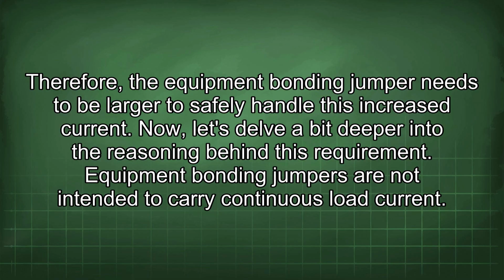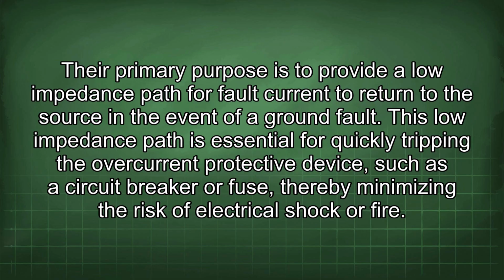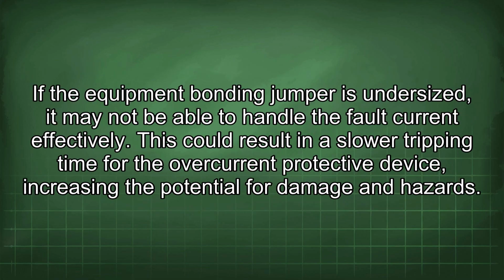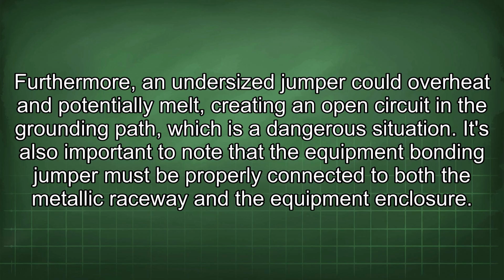Now let's delve a bit deeper into the reasoning behind this requirement. Equipment bonding jumpers are not intended to carry continuous load current. Their primary purpose is to provide a low impedance path for fault current to return to the source in the event of a ground fault. This low impedance path is essential for quickly tripping the overcurrent protective device, such as a circuit breaker or fuse, thereby minimizing the risk of electrical shock or fire. If the equipment bonding jumper is undersized, it may not be able to handle the fault current effectively. This could result in a slower tripping time for the overcurrent protective device, increasing the potential for damage and hazards.